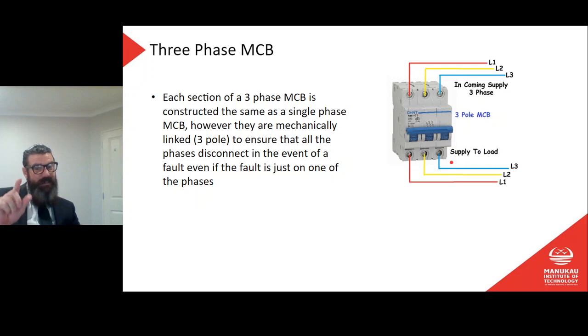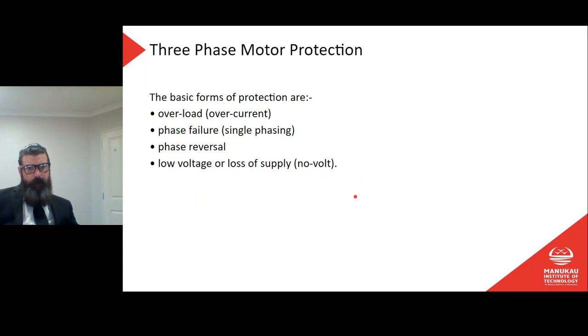I have seen three-phase breakers where it's actually just three individual circuit breakers, and then you have a little piece that slides over the top of the three individual knobs, three individual mechanisms. It slides over the top and joins them together. So that would turn three separate breakers into one three-phase breaker, and that is exactly what we have here. That's what that is doing. It's just the fact that they are joined here that makes it a three-phase breaker. Otherwise, completely separate. Pretty neat, huh?